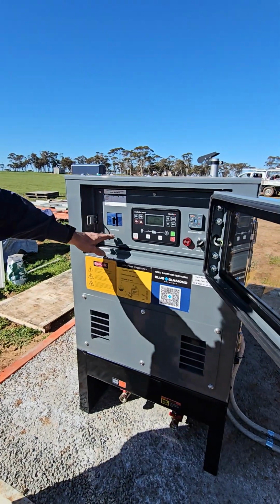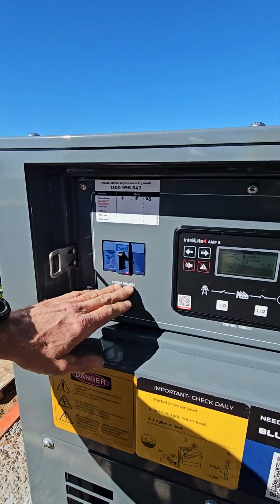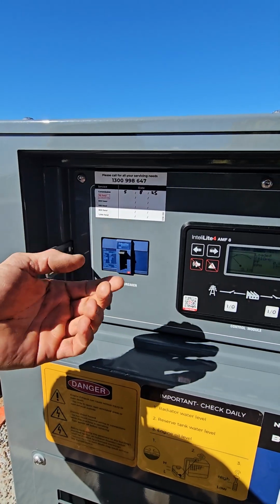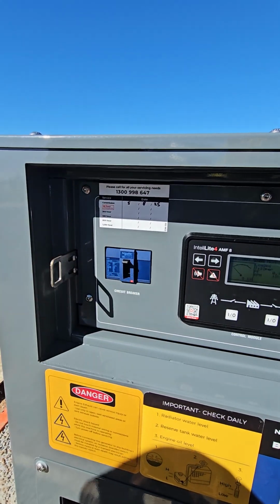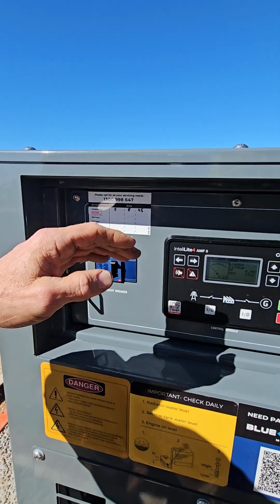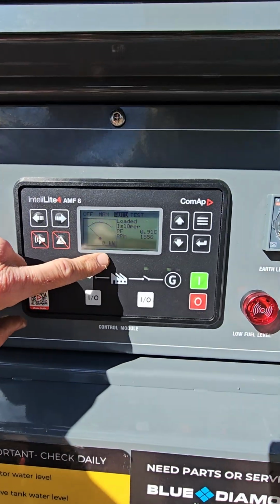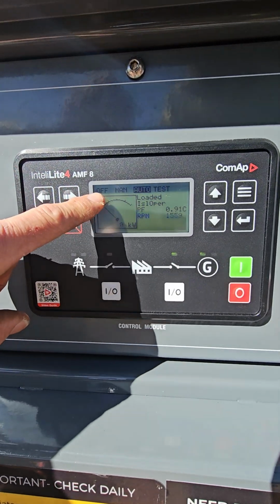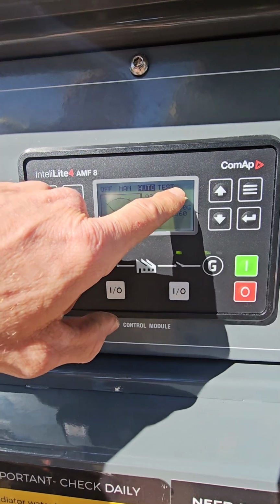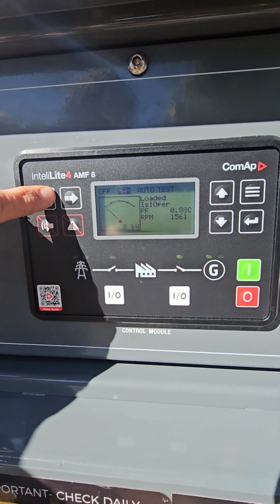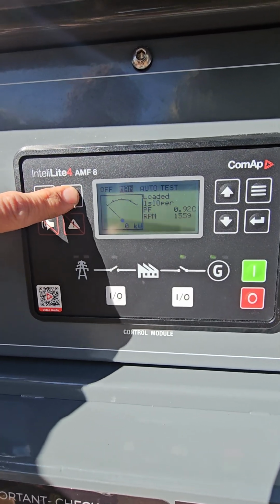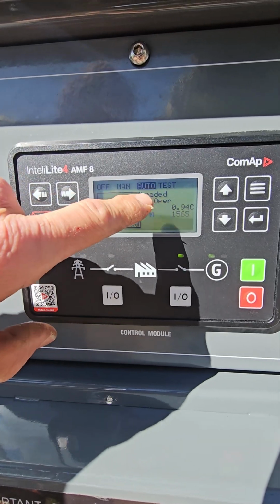And then this is your circuit breaker for the system, so if this is tripped then obviously you won't get any power out of the generator. So you make sure this is on, in the up position like it is now, to make sure that it's ready to go. So on this controller here, you can see at the top we have off, manual, auto and test. So these little buttons here, you can scroll across to the different settings. We want to leave it in auto at all times.